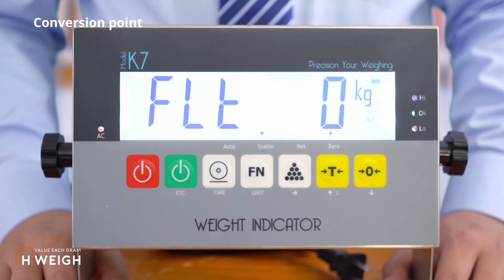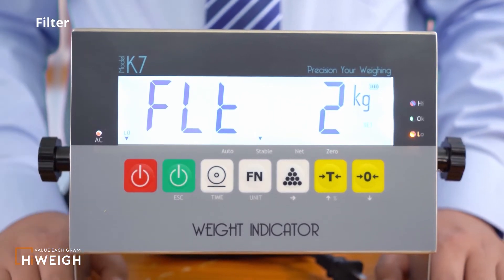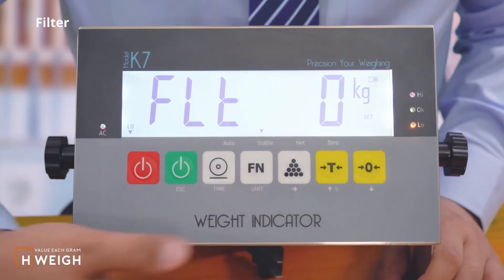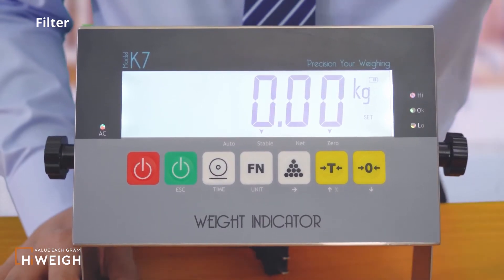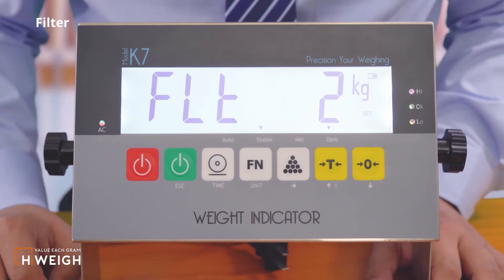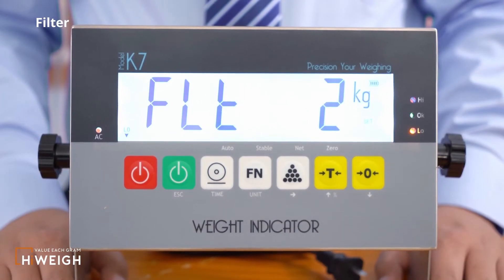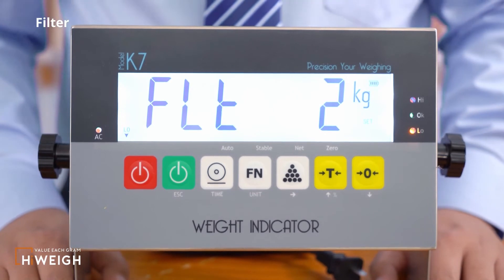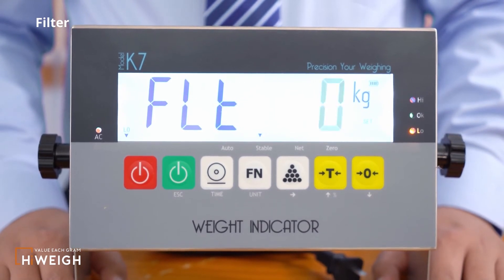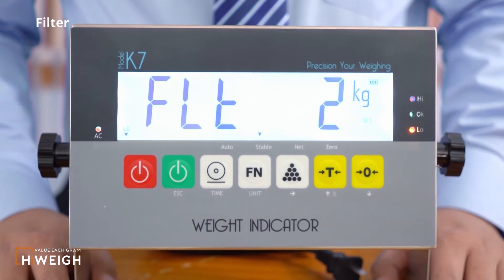The next is the configuration of the filter. What appears is the filter configuration that has been saved. There are several options for filter parameters. The smaller the value, the faster the response speed of the indicator to the weight. The larger the value, the better the stability of the value displayed by the indicator. If you want to modify it, press the accumulation button to enter the modification interface, then press the tare button or the zero button to adjust. Press the function button to save.